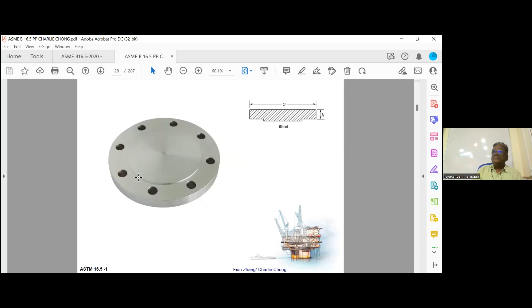Another important point is, flange will have some class. What are the classes? 150, 300, then 400, 600, 900, 1500, 2500. 16.5 covers these classes. You should remember them because in an older exam there was a question: which of the following is not a class? So you should know what classes are available. 150, 300, 400, 600, 900, 1500, 2500. Up to 1500, it covers up to 24 inch. 2500 covers up to 12 inch only. More than 24 inch, there is another code, 16.47, which is not part of our exam.